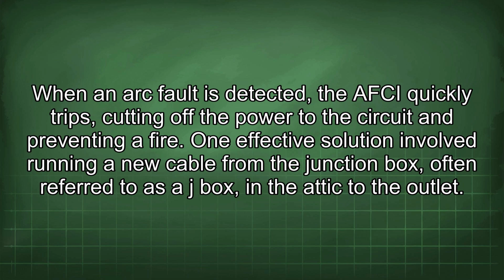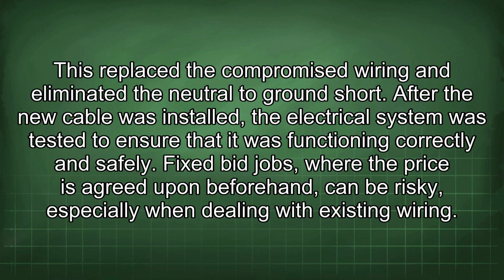One effective solution involved running a new cable from the junction box, often referred to as a J-box, in the attic to the outlet. This replaced the compromised wiring and eliminated the neutral to ground short. After the new cable was installed, the electrical system was tested to ensure that it was functioning correctly and safely.